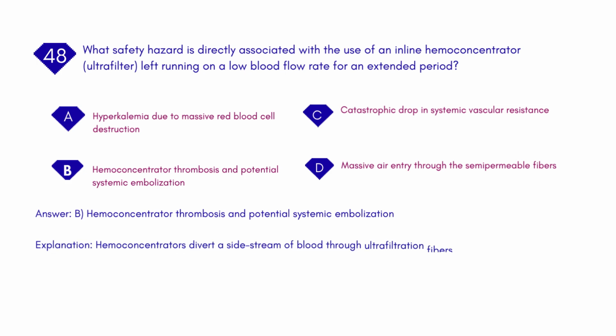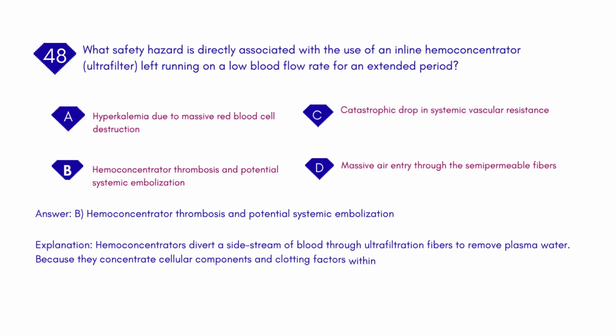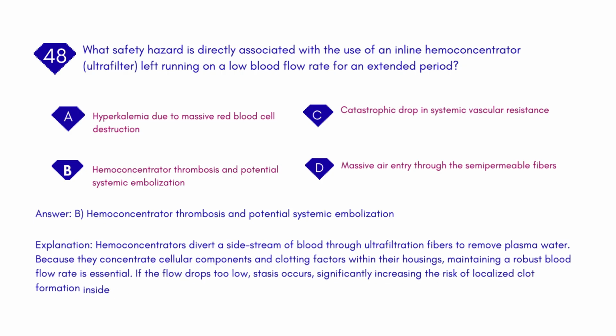Explanation: hemoconcentrators divert a side stream of blood through ultrafiltration fibers to remove plasma water. Because they concentrate cellular components and clotting factors within their housings, maintaining a robust blood flow rate is essential. If the flow drops too low, stasis occurs, significantly increasing the risk of localized clot formation inside the filter, which can compromise the device or shed thromboemboli back into the circuit.